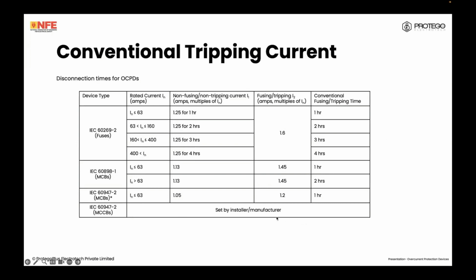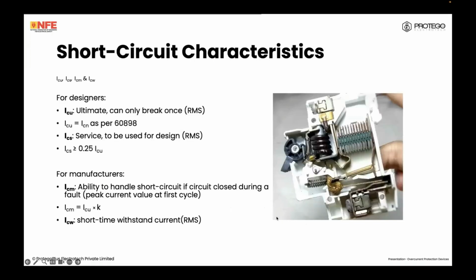Yeah, same with MCCBs, it is set by the installer or manufacturer. Now, short circuit characteristics. This is rather interesting because very often these terms are thrown around by manufacturers. So let's have a look. ICU, which is very often the rated value, and these are given as ICN for MCBs to 60898. These are the ultimate short circuit breaking capacities. Frankly speaking, the OCPDs are only designed to break these once.